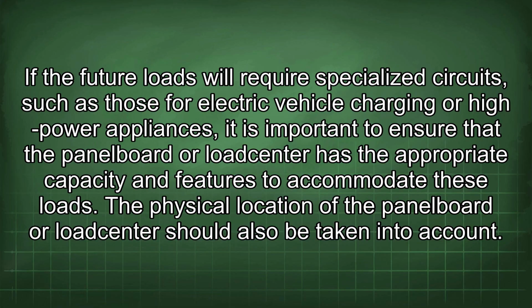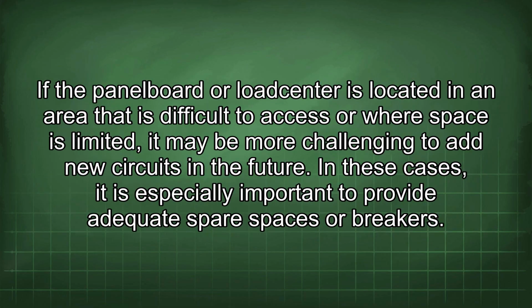The physical location of the panel board or load center should also be taken into account. If it is located in an area that is difficult to access or where space is limited, it may be more challenging to add new circuits in the future. In these cases, it is especially important to provide adequate spare spaces or breakers.